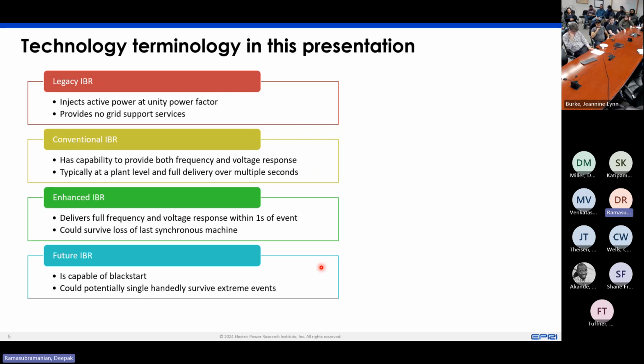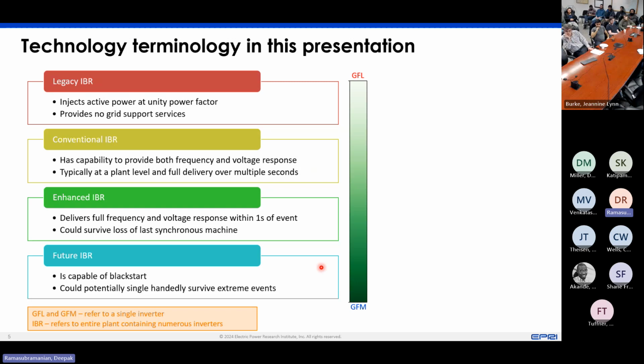If you look at these subset categories and try to map them onto the previous terminology of grid following and grid forming, what you'd essentially see is it's a spectrum. You have grid following as one bookend, denoting an inverter that can provide nothing to the grid, and grid forming as another bookend that can provide all the idealistic characteristics you want to the grid. In reality, everything lies in between.